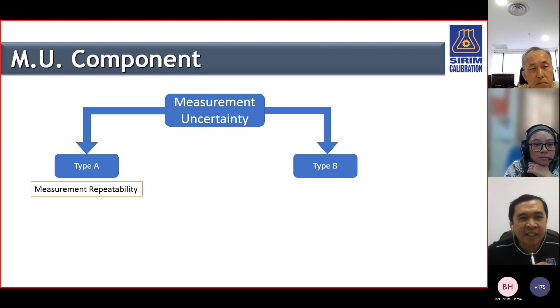And type B is the standard uncertainty. Even though the standard is used to calibrate the user equipment, please be reminded as well that the standard also has its measurement uncertainty. Standard equipment also has its error and needs correction. That's why the standard equipment has its uncertainty. From this uncertainty, we call it type B measurement uncertainty. And number two is standard drift.